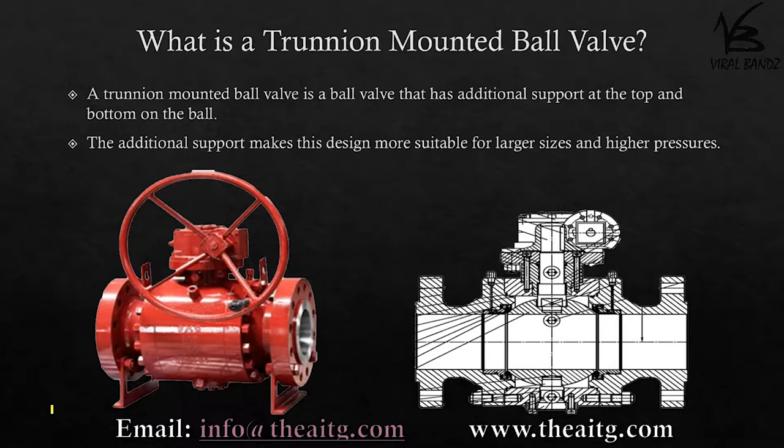A trunnion mounted ball valve is a ball valve that has additional support at the top and bottom of the ball. The additional support makes this design more suitable for larger sizes and higher pressures.